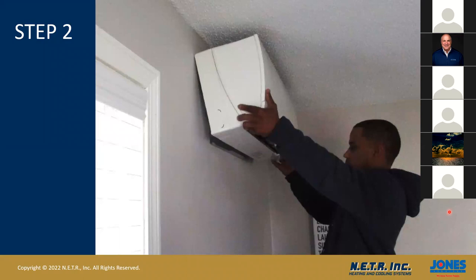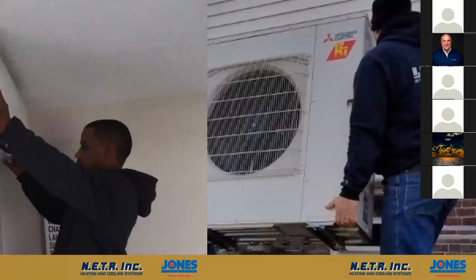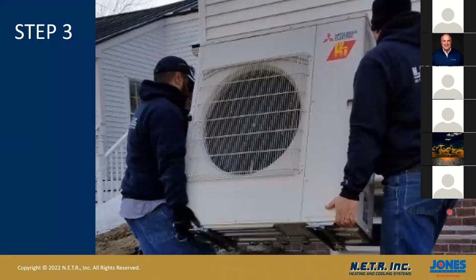How are they going to be sealed? What's going to happen? Outdoor unit would get installed on a pad, on a stand, or on a wall mount bracket. You do not want this unit sitting on the ground. Please don't let anyone install that, not on a pad, on a stand or a wall bracket, typically a stand because of snow. And I know in the New York area, stands have to be at certain heights because of certain snow loads. You don't want to be out there having to shovel around your unit in the wintertime. And to be able to defrost and drain properly as well.